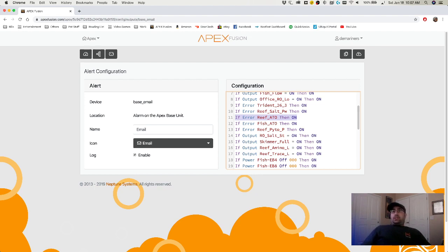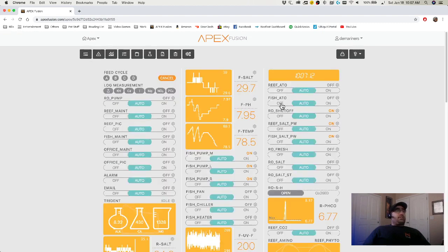Can you use another when statement to go back to auto? You cannot. The when statement only will provide an on or off, and it literally shuts off the switch. It's for safety reasons. That's the whole point that the when was developed, so that when something happens, it'll disable the outlet, or in some cases you might want to enable the outlet if it's been on for a period of time or been off for a period of time.